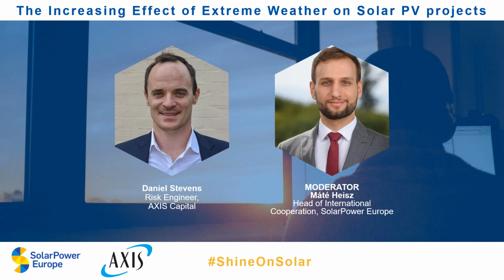That said, it can be a bit of a grey area sometimes. To give a similar example, we've been involved in a project where the grid went out for a long time, and that resulted in no HVAC, no dehumidification, no air conditioning in the inverter cabins overnight. It was in a tropical location, so at night condensation built up and attacked the power control systems, which started rusting. In that case, it actually led back to a warranty claim on the OEM, because the site was still quite new, to replace the broken components.